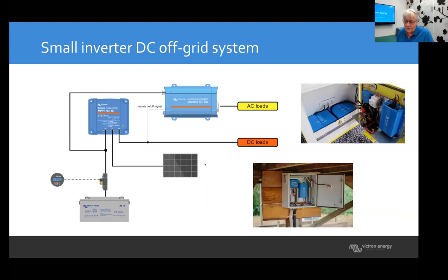Small inverter off-grid system. Again, this time we're using the load output of an MPPT, so we have a small MPPT. It runs the DC loads, but we also have an inverter in the system. The inverter cannot be connected straight to this load output because this is only rated at 10 or 15 amps, and a small inverter will easily take more than that on the DC side.